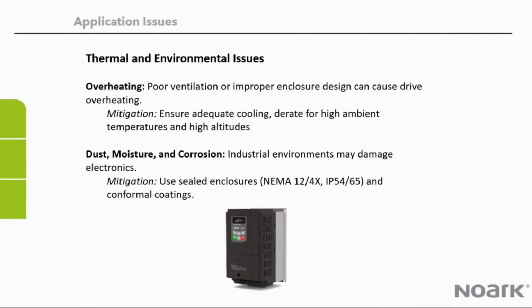Things to consider when you're determining your application. Your drive will generate heat. We need to make sure that we can shed the heat in an appropriate manner to allow reliable operation and maintain a long lifespan. Depending on the instance, our drives here have the capability of, with a kit, being installed by themselves into a NEMA 1 environment. But in other environments, you may need to enclose them. So you will need to consider the size of your enclosure to help dissipate the heat, and any other external cooling methods, venting, air conditioning, fans, things of that nature to maintain a proper operating temperature.